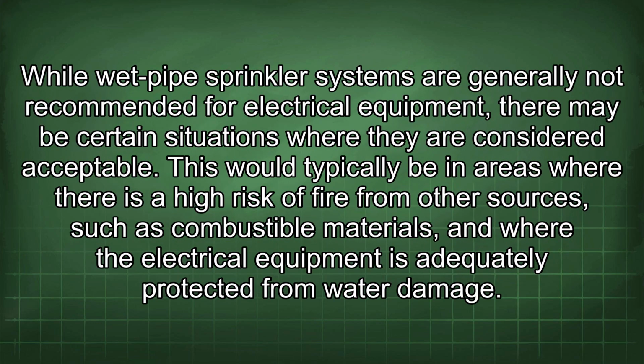While wet pipe sprinkler systems are generally not recommended for electrical equipment, there may be certain situations where they are considered acceptable. This would typically be in areas where there is a high risk of fire from other sources, such as combustible materials, and where the electrical equipment is adequately protected from water damage.